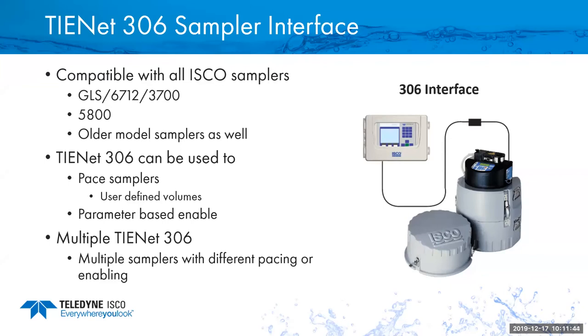You can actually connect multiple 306s, again, up to the 9 different TIENet devices on the signature meter. So if you have 2 samplers that need to be paced, one for a municipality and one for your own sampling, just getting 2 306 sampler interfaces and setting them up, you're able to pace both samplers and do that with ease.